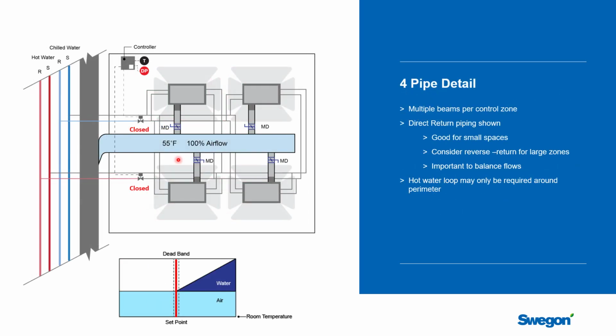Well, let's talk about a 4-pipe chilled beam system in here. Now we've got both a chilled water loop and a hot water loop distributed throughout the building. And in here, the system is neutral. The temperature is being met, so we have no heating and no cooling. So both the hot water and the chilled water valves are closed. And you're getting a little bit of cooling from this primary air, this 55-degree air that's going into the space. So there's a little bit of cooling going on. And so the controller can use these 2 valves to modulate it.